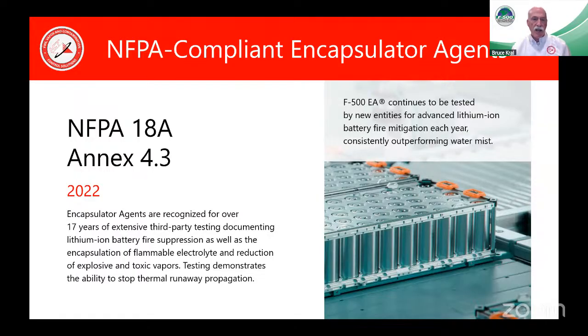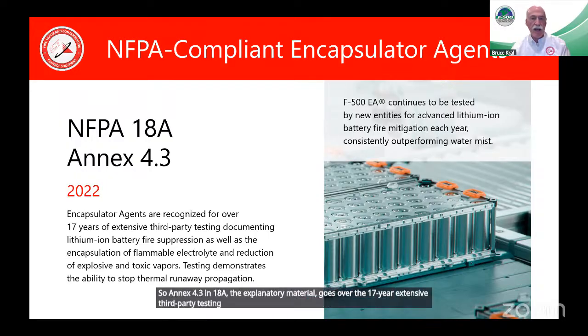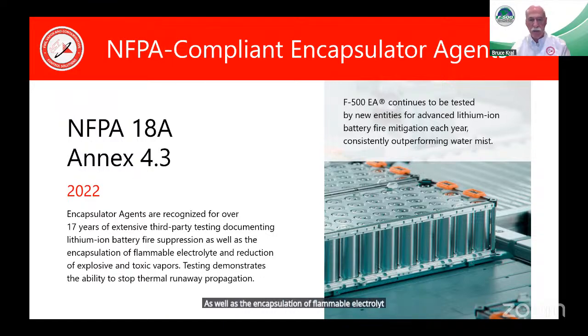Annex 4.3 in 18A, the explanatory material, goes over 17 years of extensive third-party testing documenting lithium-ion battery fire suppression, as well as the encapsulation of flammable electrolytes and flammable liquids. The test itself demonstrates the ability to stop thermal runaway propagation.